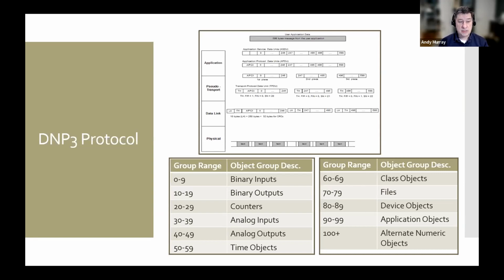Modbus and DNP are still actively maintained protocols, but DNP is, I would say, more active. There's a newer addition to DNP, maybe around for 10 years now, and they came out with a new revision recently called DNP SA. The SA provides some authentication, message integrity, and encryption built into the protocol, though the industry is getting a very slow response to bring this online, unfortunately. I've seen maybe 2 or 3 of the devices I typically use that have this as an option, but I don't have a system yet that actually uses the protocol actively.